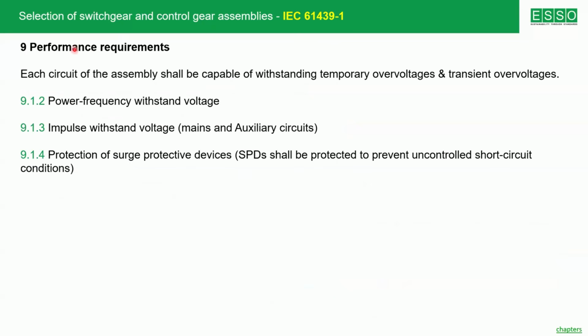resulting in fire or accident. Similarly, in the switchgear and control gear assembly, another requirement related to earthing is in clause 9.1.2, power frequency withstand voltage. Because during a high voltage fault, the transfer potentials will affect the low voltage side. The maximum limits are already defined in the standard. Now imagine the maximum power frequency stress voltage due to a high voltage fault is 1200 volt. Now your equipment must be able to withstand 1500 volt for a certain time. So this is of course related to the earthing.